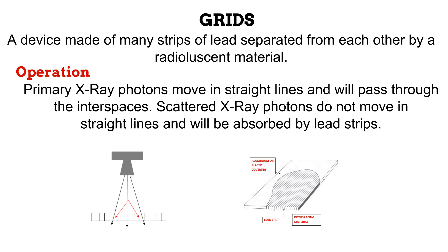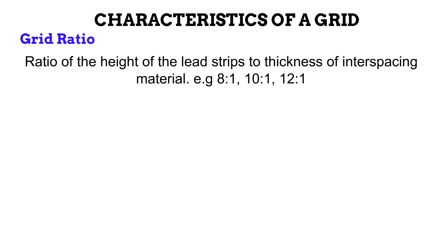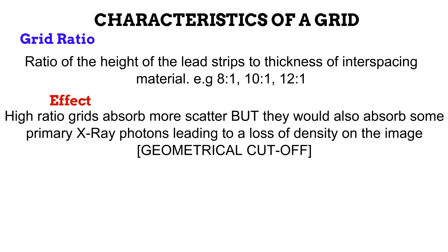Grids have certain characteristics that determine how they function. The first is the grid ratio — the ratio of the height of the lead strips to the thickness of the interspacing material. Note that the height of the lead strips refers to its thickness. You'd find grid ratios such as 8:1, 10:1, and 12:1. The higher the grid ratio, the more scatter is absorbed, because a high grid ratio means thicker lead strips, which absorb more scatter than thin ones.